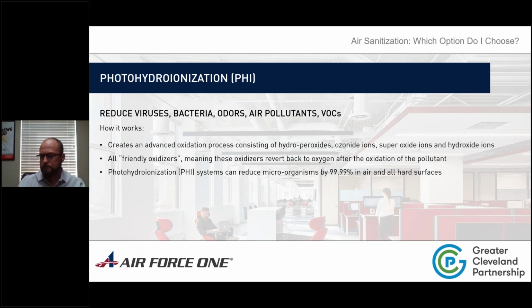Yeah, Brian, I want to touch on one point. One of the big negatives that people bring up, whether it's PCO or PHI, are the ozonide ions, which is ozone, or O3. That only gets generated if you're using a standard fluorescent or compact fluorescent form of UV generation - that's actually part of the UV process. If you're using most of the newer technologies, they use LEDs, which do not produce ozonide ions or ozone. It's very important to select one that doesn't produce ozone. Although ozone is a great oxidizer and helps the sanitization process, it can also be hard on people who have respiratory illnesses. So it's very important to make sure you're using one that's LED based, and then that's a non-factor. That's a good point.